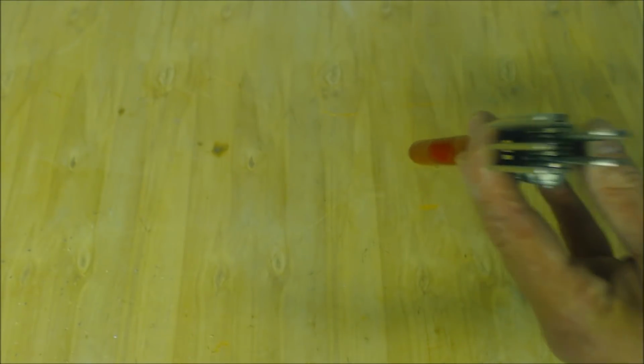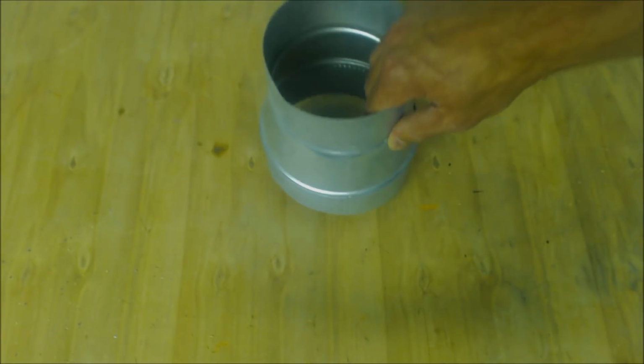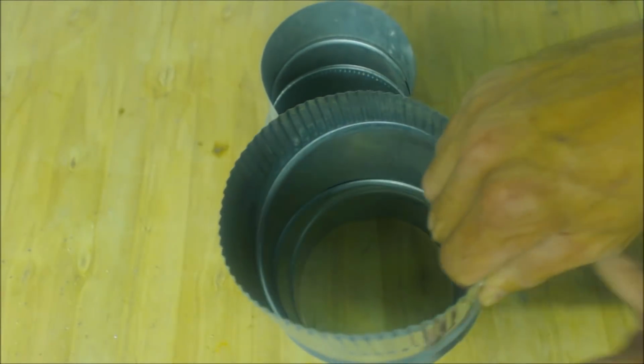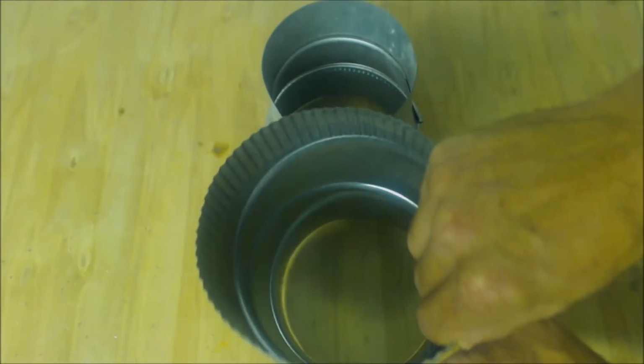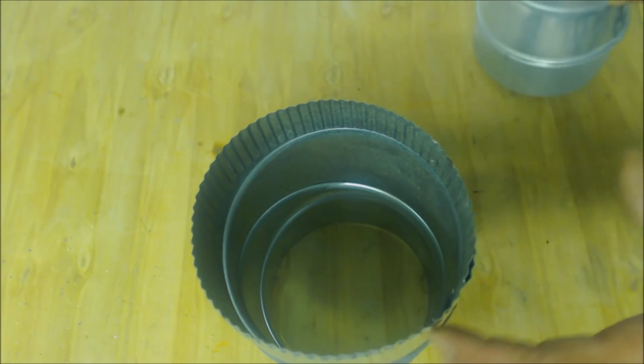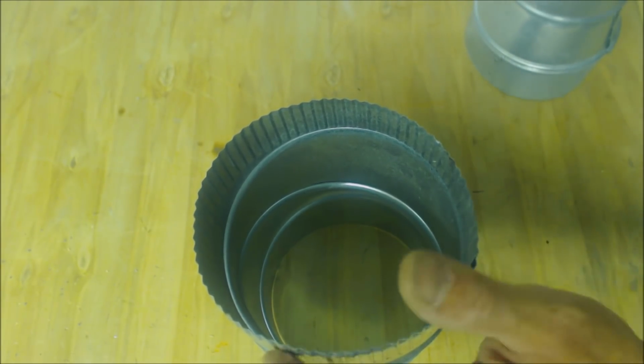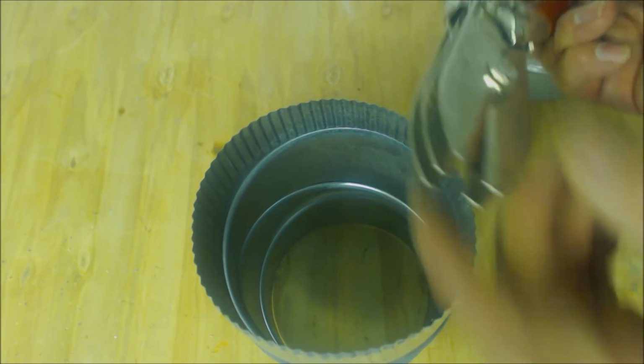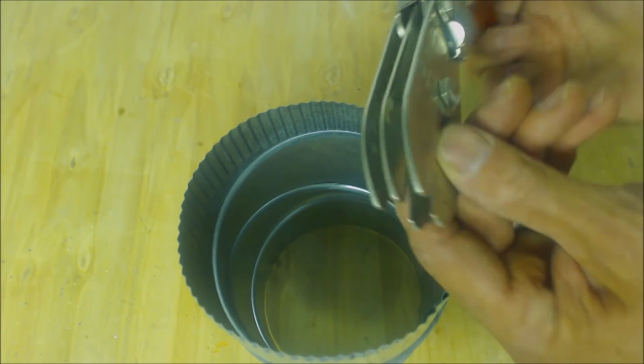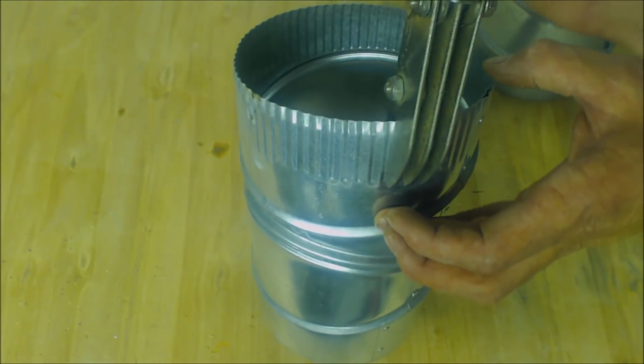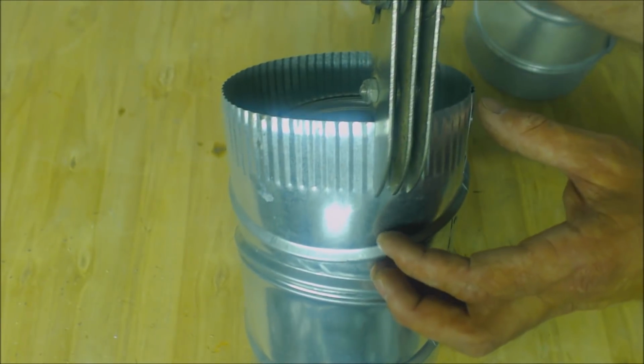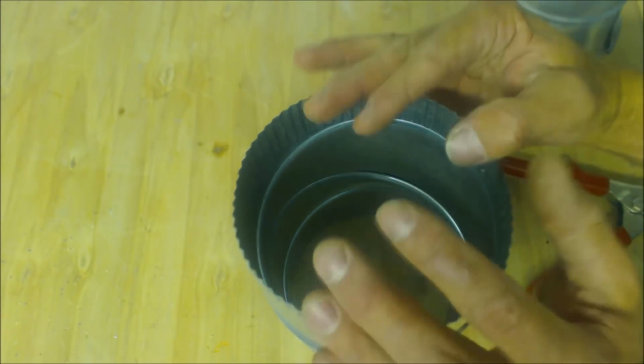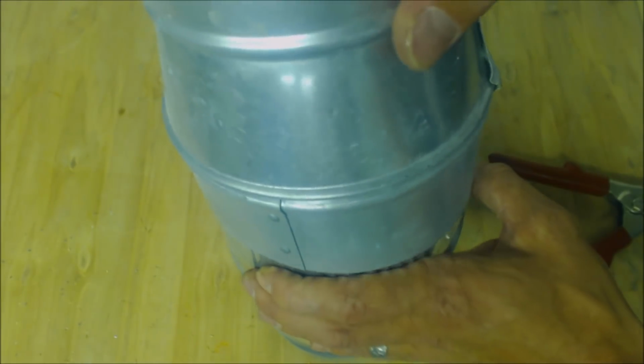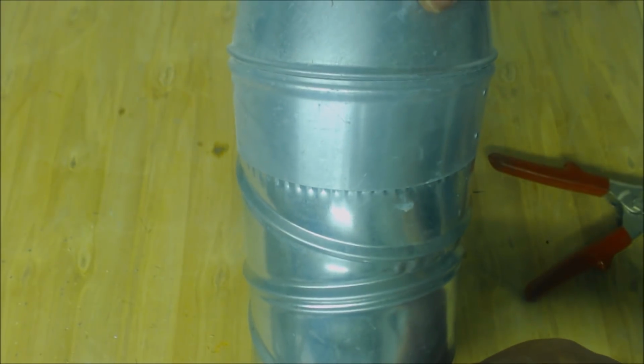Next is the 5-blade crimpers - you have 3 blades on one side and 2 on the other. If I wanted to put this reducer on top of this adjustable 90 right here, so it can turn into a 90-degree elbow, this already has the 5-blade crimps in it from a crimping machine. If we wanted to increase the crimps to fold it in more, we'd take the 2-blade side and put it on the inside, and it actually pulls the metal together and folds it that way. This fits snugly on there just like that.